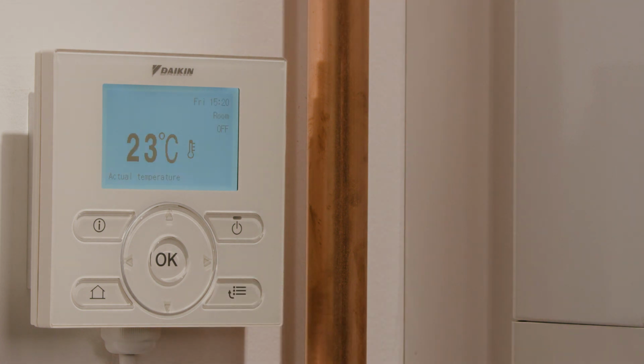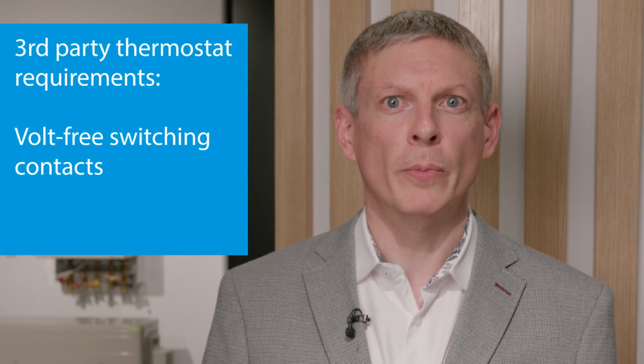Room temperature control is either from the Daikin controller or a third-party thermostat. If a third-party thermostat is used, it must be volt-free and TPI disabled, or with the ability to disable the TPI functionality. The system is cloud-ready with the optional LAN adapter, which allows the system to be controlled from the Onecta smartphone app. When connected to the Onecta app, you can both control and monitor the system from anywhere.